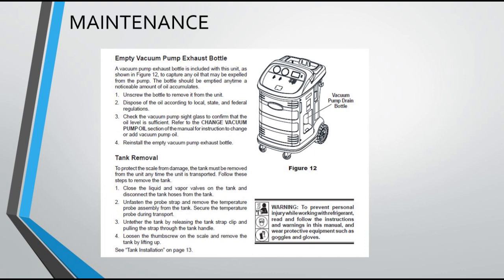Tank removal. To protect the scale from damage, the tank must be removed from the unit anytime the unit is transported. Close the liquid and vapor valves on the tank and disconnect the tank hoses from the tank. Unfasten the probe strap and remove the temperature probe assembly from the tank. Secure the temperature probe during transport. Untether the tank by releasing the tank strap clip and pulling the strap through the tank handle. Loosen the thumb screw on the scale and remove the tank by lifting up. See tank installation on previous pages.